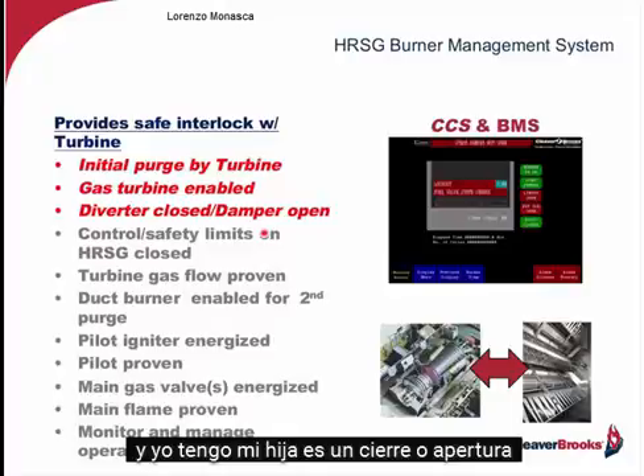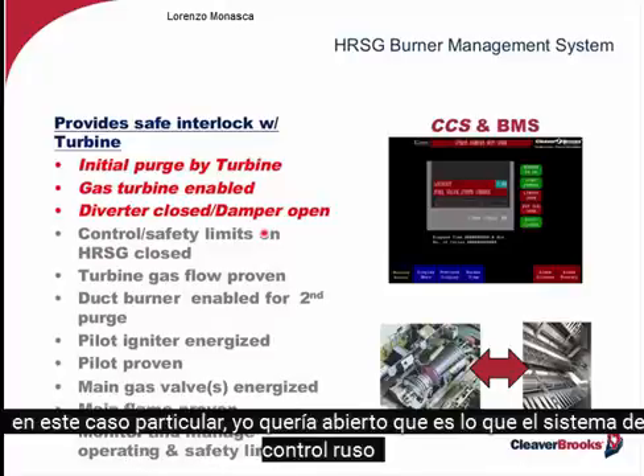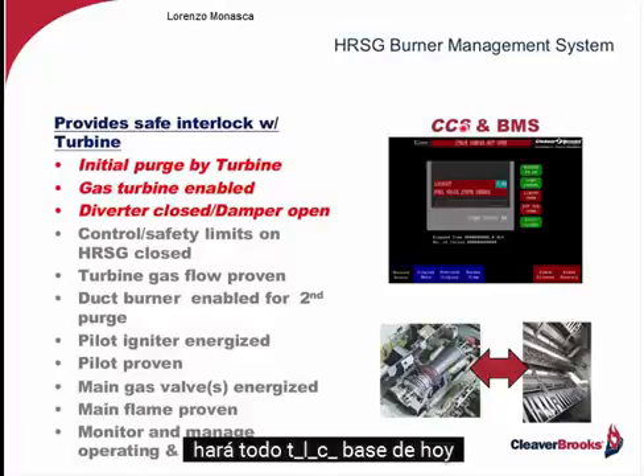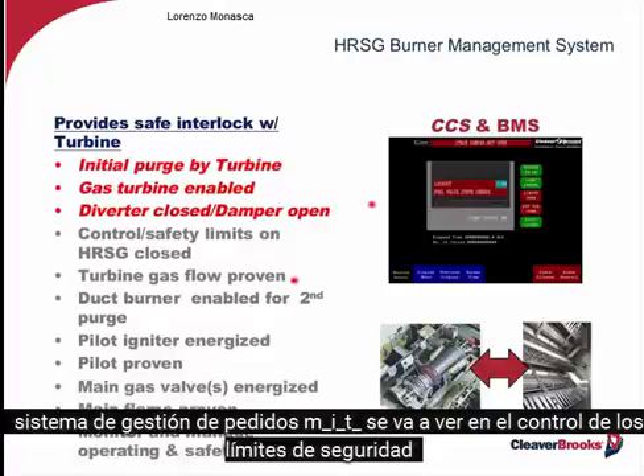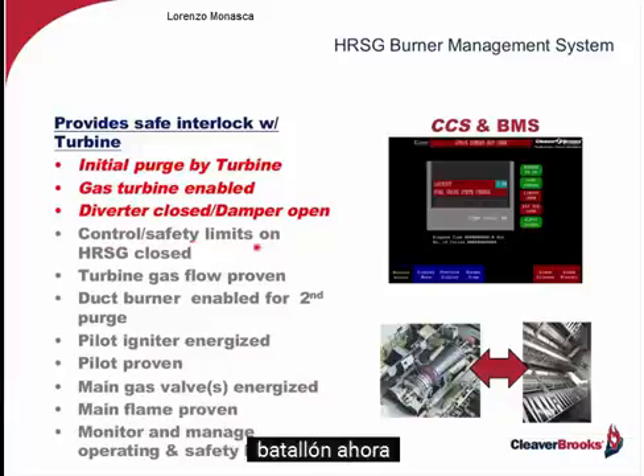Then I've got my diverter. Is it closed or open? In this particular case, I want it open. That's what my combustion control system will do. All PLC based today. Then my burner management system is going to look at the control and safety limits that tie in now to my duct burner.